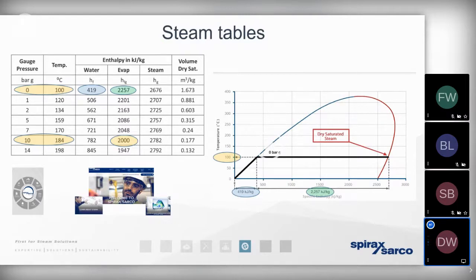Second reason is, well, we may need to protect the heat exchanger from exceeding its maximum working pressure. For example, if the heat exchanger is rated to 10 bar gauge, we're going to have problems if it's exposed to a pressure that is significantly greater. So we need to reduce the pressure for that reason. But the other reasons are slightly less apparent, and they're more apparent by referring to the steam tables.